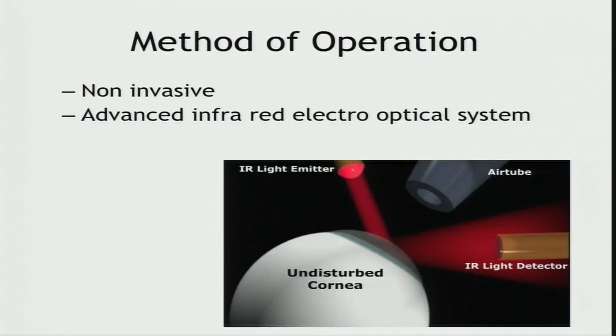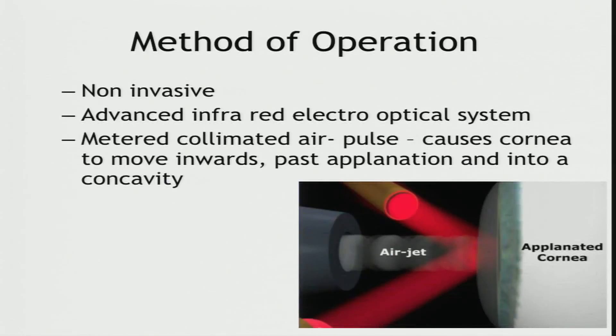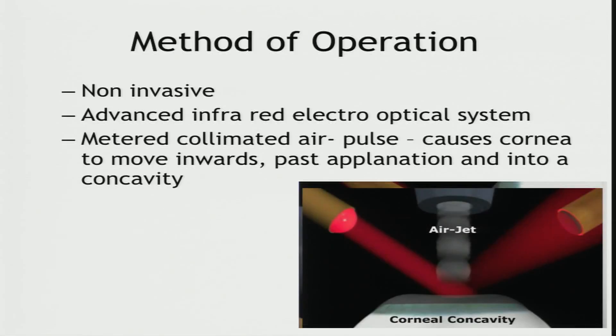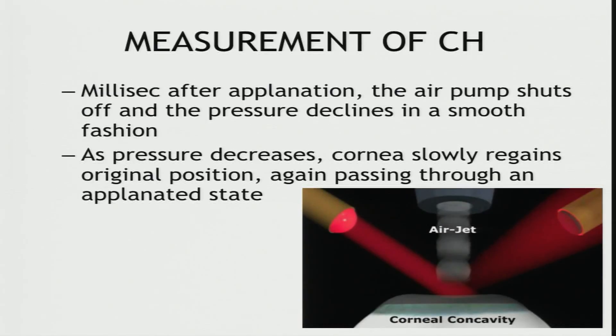This is how it is done. It's a non-invasive process with an advanced infrared electro-optical system. In a normal state, the infrared light which falls on the cornea is not detected by the detector. A metered collimated air pulse causes the cornea to move inwards, which first applanates — that is, it flattens — then passes beyond the point of applanation to produce concavity. At this point of applanation, the infrared light is detected by the detector. After this applanation is produced, the air pump is shut off and the pressure declines in a smooth pattern. As the pressure decreases, the cornea slowly regains its original position, again passing through the applanated state, at which it is again detected.